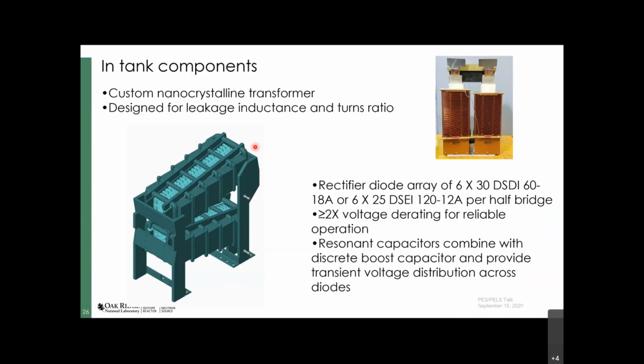I mentioned the rectifier assembly already. This is it shown: each card is a printed circuit board with 6 series-connected diodes on it, and they're all lined up in a cassette. So we can have up to 180 series-connected diodes per half bridge in this application, giving about a factor 2 voltage derating and resulting in fairly reliable operation.